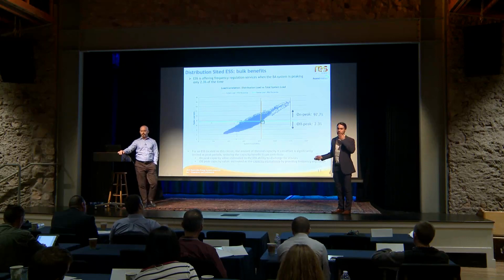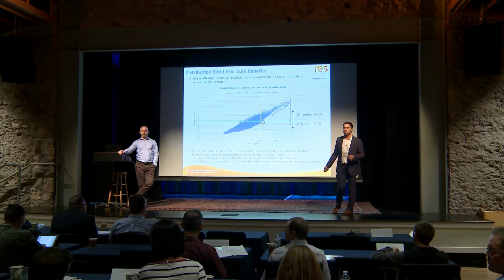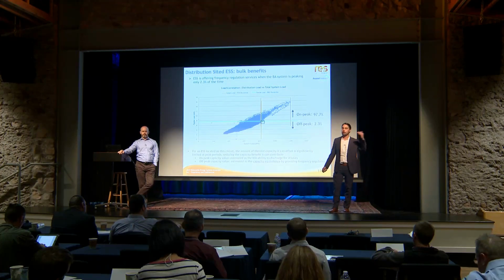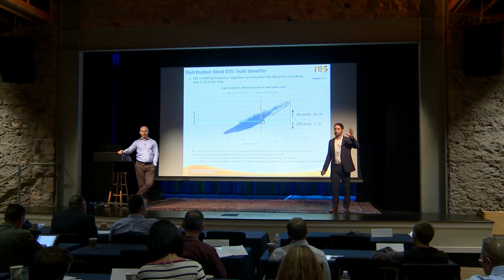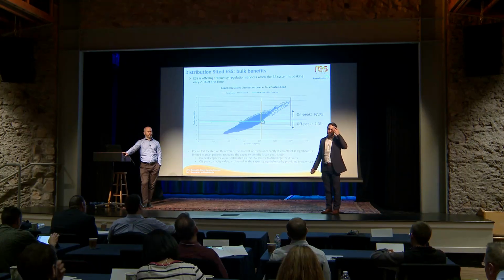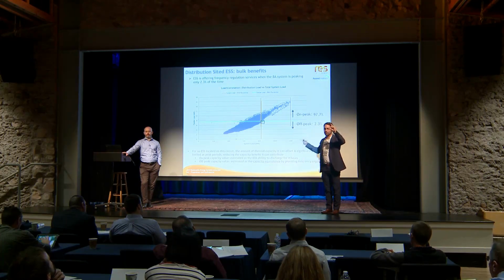Let's say your distribution system wasn't restricted, only restricted when the load exceeded a certain value - that restriction is when... that restriction was 100% then? Well, it's only at times when the distribution load is peaking. Here's a simple example: a 10 MVA circuit with a transformer of 10 MVA capacity, and the load is 90% of the time below 8 megawatts. So we said, okay, on this circuit we can do 2 megawatts all the time except when the load exceeds that 90th percentile - we'll take it out of market during those times.